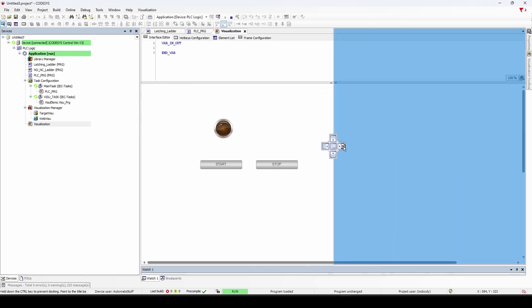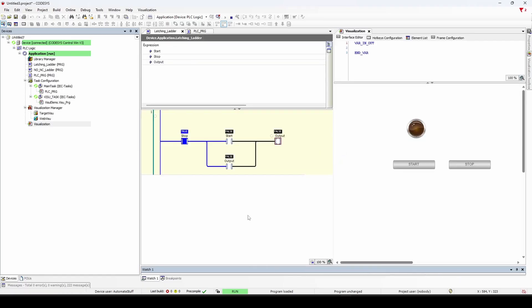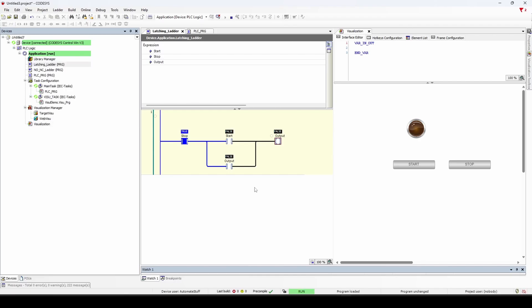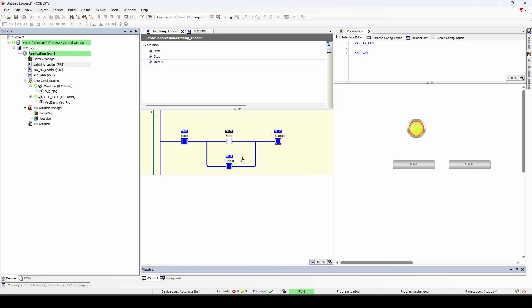So we're latching correctly. It's doing what we want it to. And let's see the logic with the buttons side by side. We hit start. You can see that we energize that momentarily. It turns on the output coil, which then allows the circuit to stay latched because this output contact goes true. And if we hit stop, you can see the light goes off because our stop goes momentarily false, breaking that circuit. I hope this was useful and you learned something. And I'll see you in the next one.